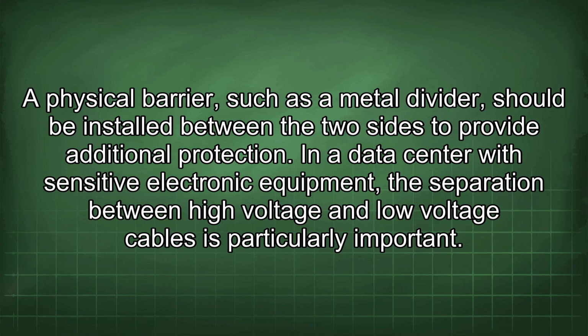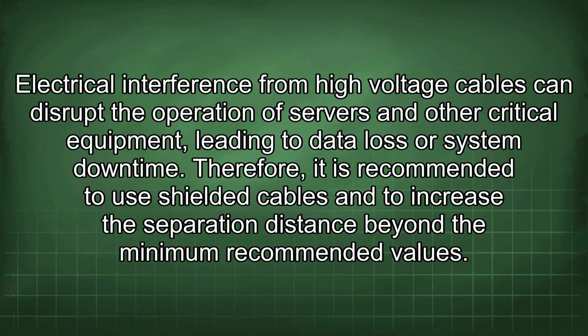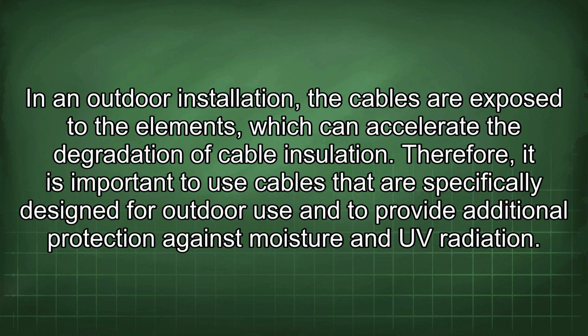In a data center with sensitive electronic equipment, the separation between high voltage and low voltage cables is particularly important. Electrical interference from high voltage cables can disrupt the operation of servers and other critical equipment, leading to data loss or system downtime. Therefore, it is recommended to use shielded cables and to increase the separation distance beyond the minimum recommended values.